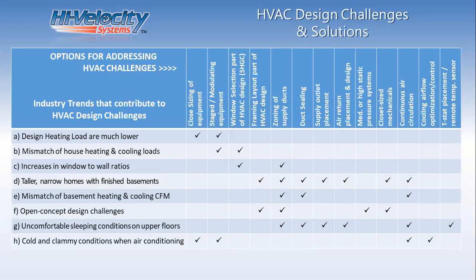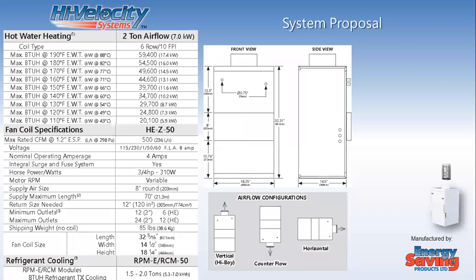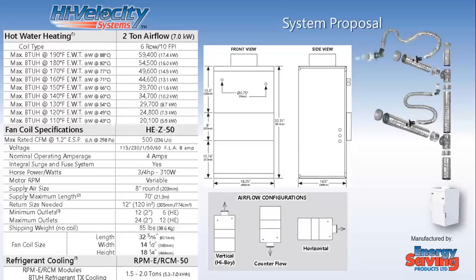But the solution that I'm going to talk about right now for this low-load home tackles all of these HVAC options and challenges through our small duct high velocity solution. Right off the bat, being a fan coil, we can specifically select the BTU output based on water temperature if we elect to use hot water heating, which is in the northern US and Canada the most popular option to go. Down in southern US, heat pump is certainly the most popular way of heating most structures.